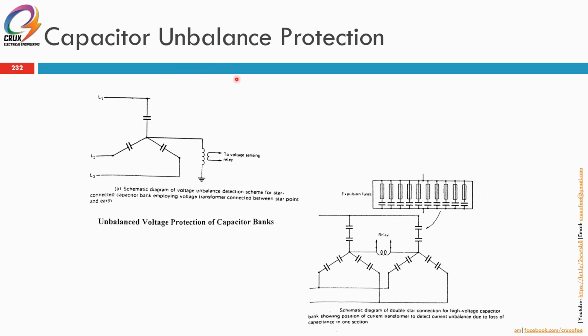Capacitor unbalance protection. This is a star connected capacitor. Under normal conditions, if your capacitors are healthy and working normally, the star point here will have zero current. Let's say one of your capacitors is shorted or open circuited. Then there will be a current circulating here. This current may go back to the ground, or if there's a short circuit, go back to ground, and this will trigger the voltage sensing relay. Alright.